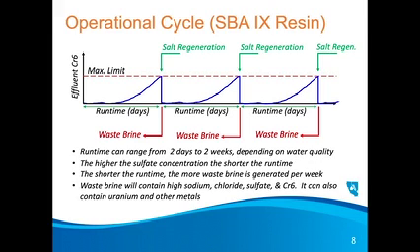Obviously, everything you removed from the water is now concentrated in that brine, and that becomes really the tail that wags the dog. That becomes the challenge with whether this is a process that's going to work for a specific system, or it's got a fatal flaw because of the disposal requirements of that resin.